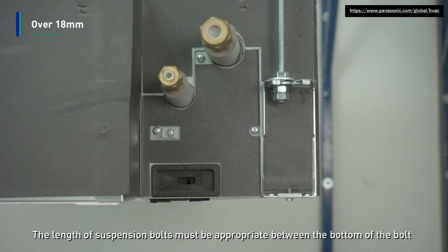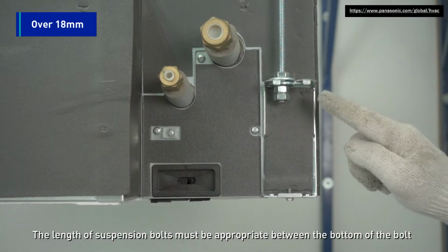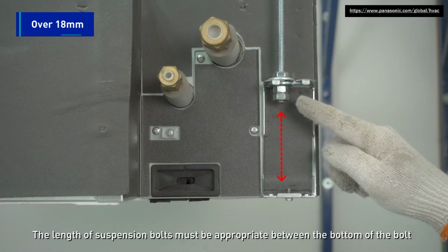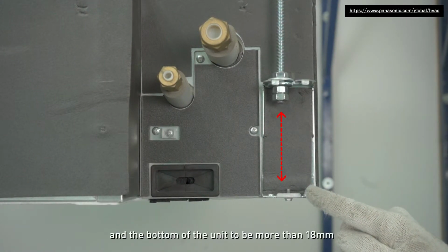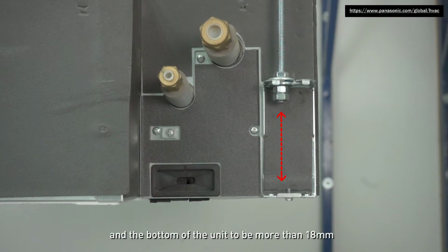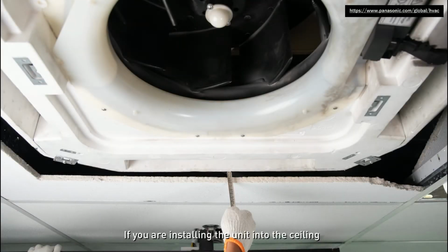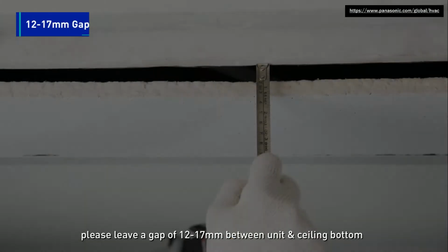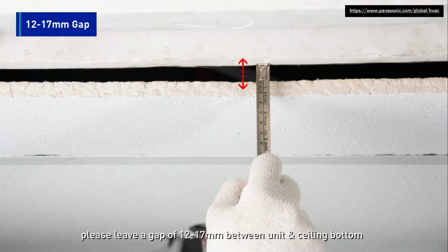The length of suspension bolt must be appropriate between the bottom of the bolt and the bottom of the unit to be more than 18 mm. If you are installing the unit into the ceiling, please leave a gap of 12 to 17 mm between unit and ceiling bottom.